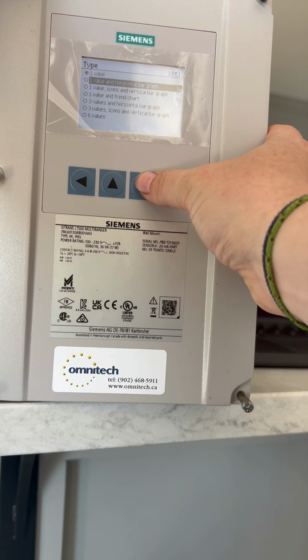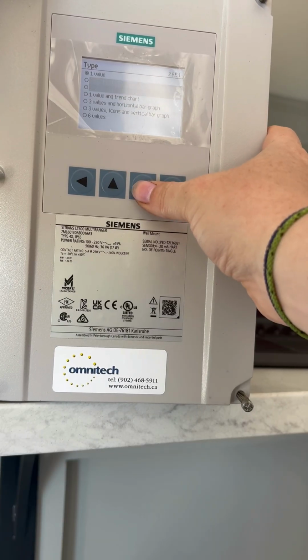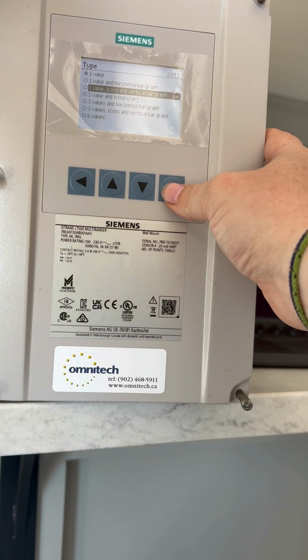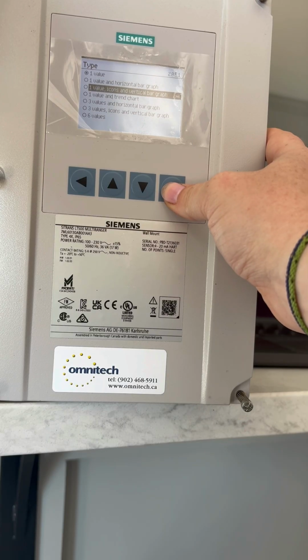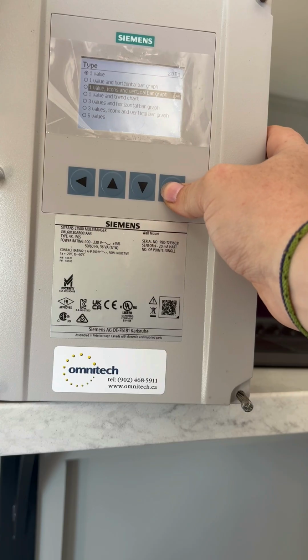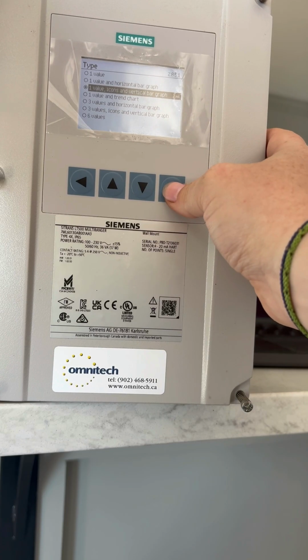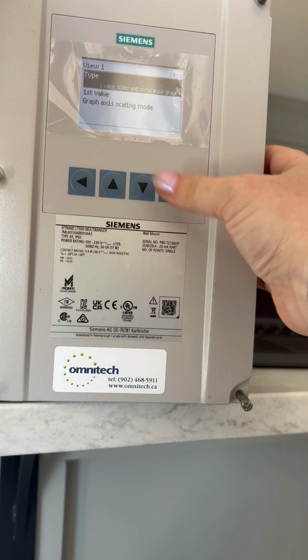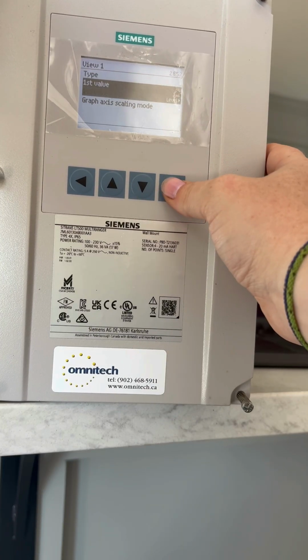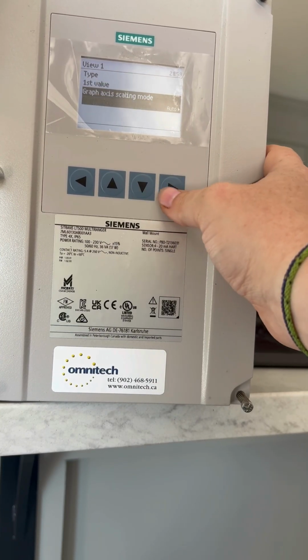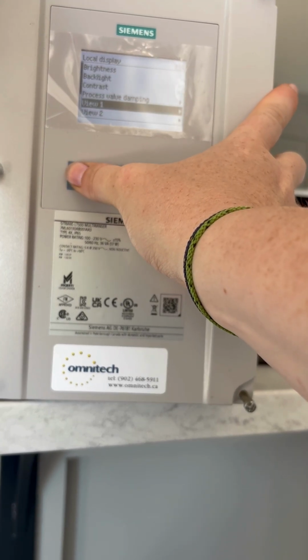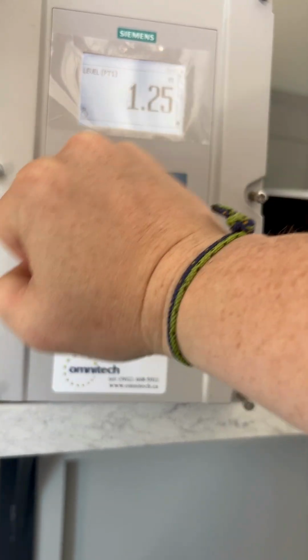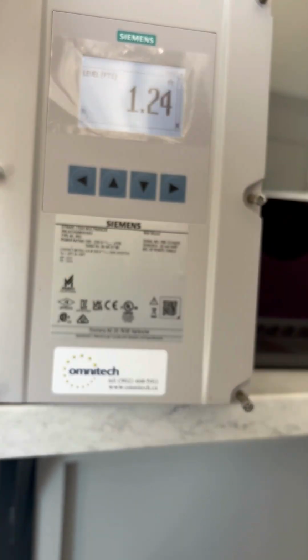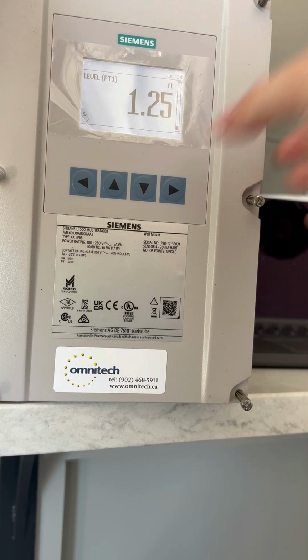My type of value, I actually want to have a value, icons, and vertical bar graph because I want to show that I have a relay activated on that first screen if I do have one, or if it's open, like if it's not being used. So there we go. We're going to go into there. I've clicked enter, and I clicked enter again. First value is going to be level. That's correct. And I'm just going to let it auto scale the graph because I don't need it to be specifically different. So now you can go back and you can see that view 1 now shows that graph bar and now shows that relay 1 is set up, but it is open.